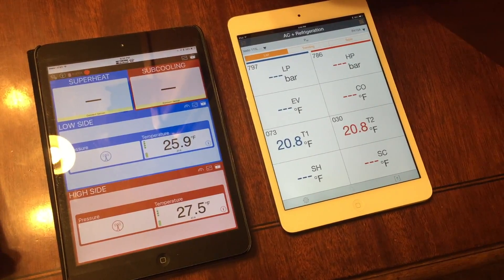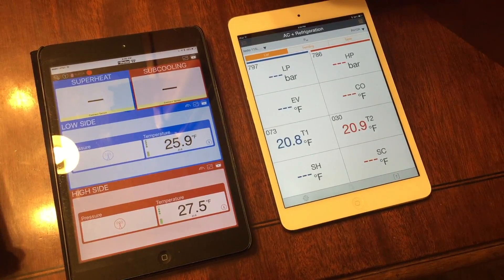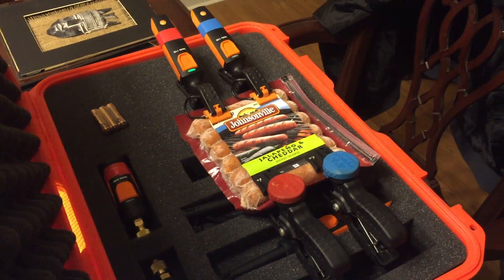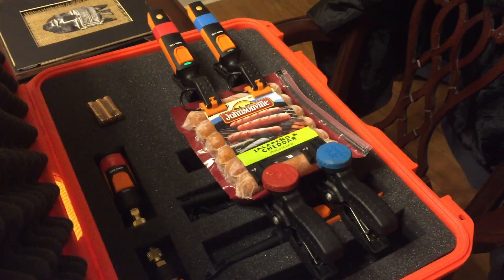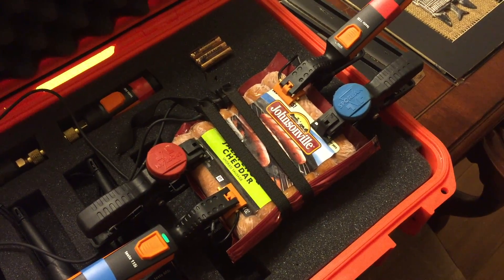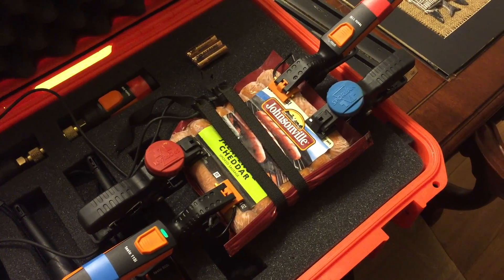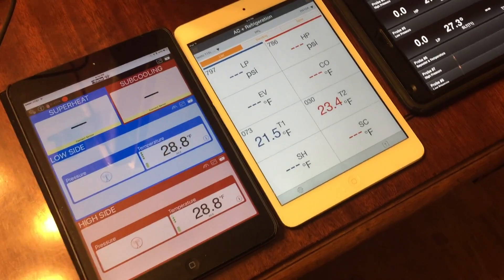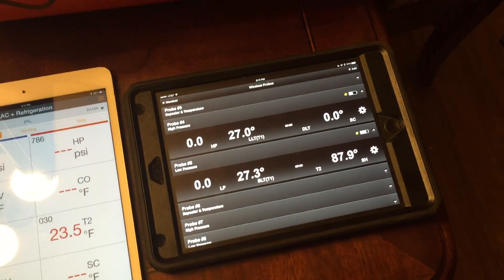You guys would probably do well to switch back and forth or rewind and fast forward to compare the numbers. But that's the best I can do — put them all on a piece of Johnsonville Jalapeno Cheddar Bratwurst that literally just came out of the freezer a few minutes ago. I added the iManifold probes and moved one of the Testos and one of the Sporlans to the other Bratwurst. The Sporlan now agrees. The Testo has a variation of about 2 degrees, and the iManifold has a 3 tenths of a degree variation between the two sensors, with about half a degree variation overall.